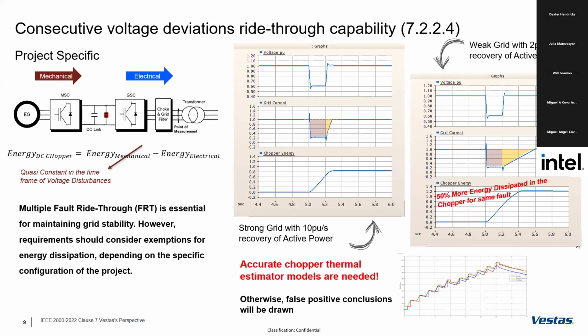Having said that, if I test this in a generic model, I will ride through 1 million faults, because the first fault will be identical to the fault 100 or 1 million, as long as there are no grid instabilities in voltage. But my weaker point from an OEM design perspective, that is the thermal part, is not being considered. So what if I include the thermal model?